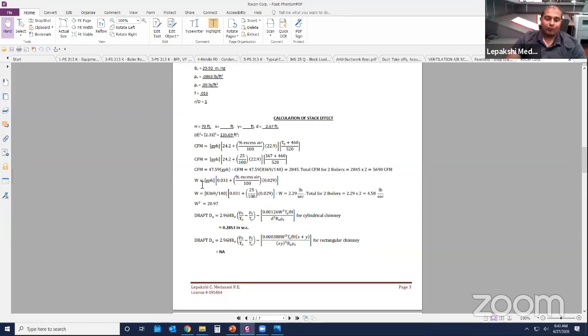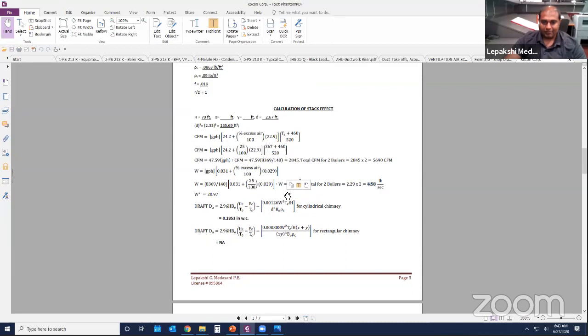Now, what would be the weight of that stuff? You calculate the weight of the flue gases too, using the formulas. I figured in a 25% excess air just for combustion purposes—for instance, if you need 100% air for combustion, I'm adding 25% excess air just for effective combustion. We don't worry about excessive combustion, just account for that excess air.